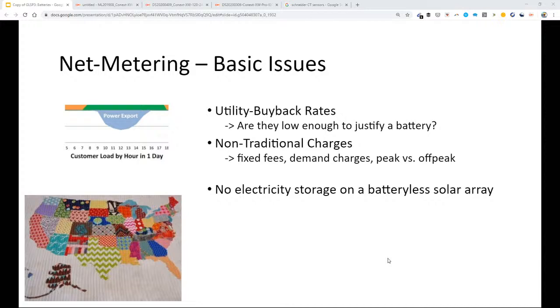But a solar array without a battery cannot store its power, and that makes it kind of a dumb device rather than a smart device. A solar array just wants to dump all of its power onto the grid, and that's it. If the grid's not there to take it, it has safety measures built into its circuits to prevent it from operating. So a solar array without a grid to tie into, whether it be the grid or a separate battery inverter, can't turn on. And furthermore, when it does turn on, it wants to dump everything it has into that power source, and the power source has to be stable enough to take it.